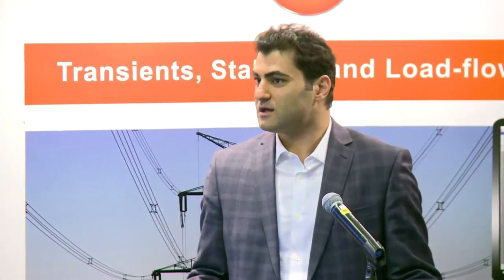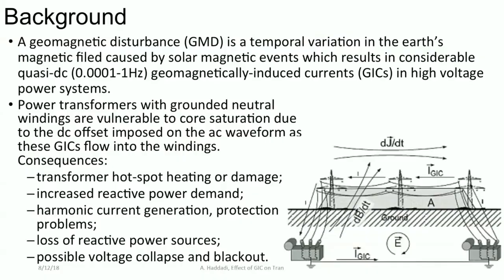From the viewpoint of a power system engineer, these changes can be modeled as a moving box of currents above the Earth's surface — about 100 kilometers above the surface — and the magnitude of this current could be up to 1 million amps. This current has a very small frequency, in the range of millihertz.